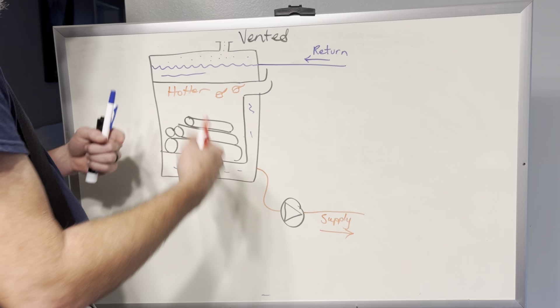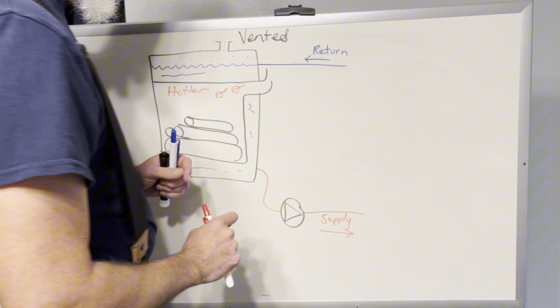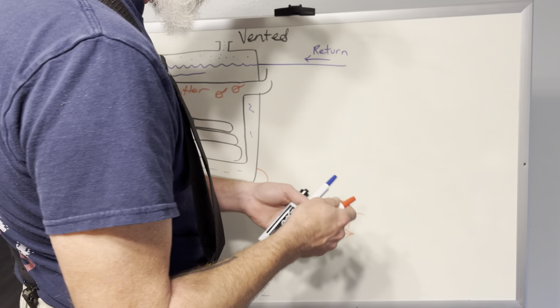remember, we'll talk about counterflow. You want the hottest temperature of the boiler to be exposed to the coldest water, a counterflow. So we bring the return water in here. One reason why you might want to do this is you're going to have better heat transfer. Basically, the temperature difference between the water you're trying to heat and the fire you're trying to heat it with, counterflow arrangements keep that difference between the two highest for the longest amount of time.